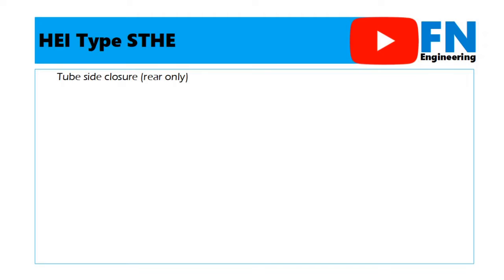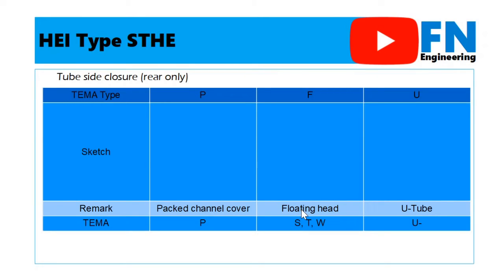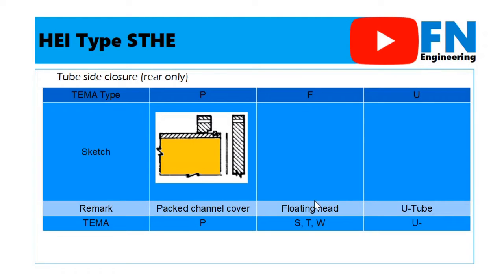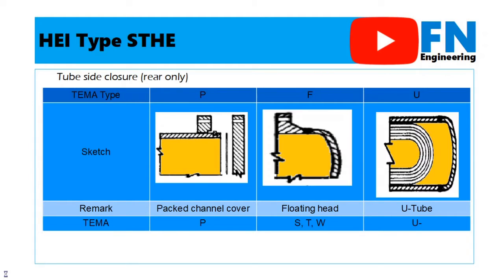Now turn to the tube side closure for rear head only. There are 3 types, namely type P, type F, and type U. Type P is a packed channel cover. It is similar to type P in the TEMA standard. Then, type F is a floating head. The type is typical with type S, type T, and type W. The last type is type U, or U-tube shell and tube. It is also similar to type U in the TEMA standard.